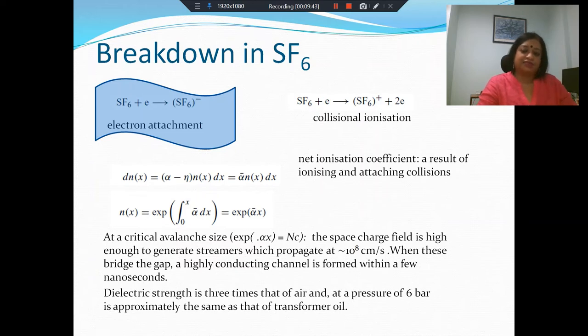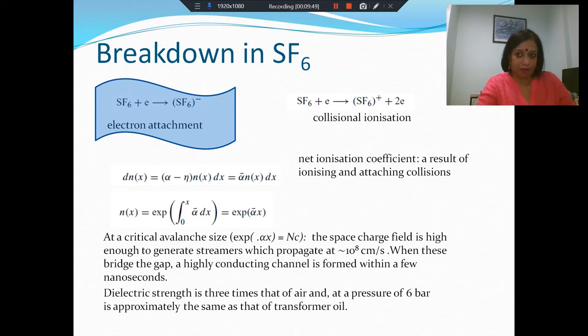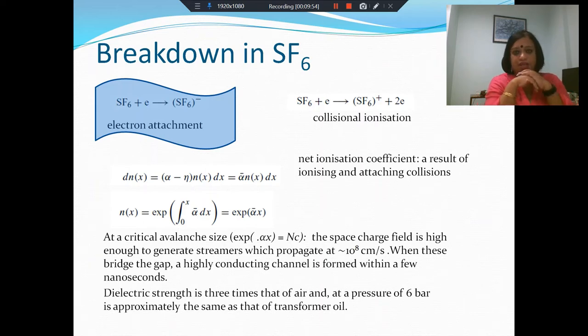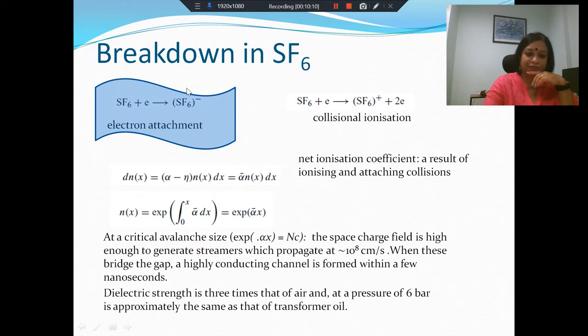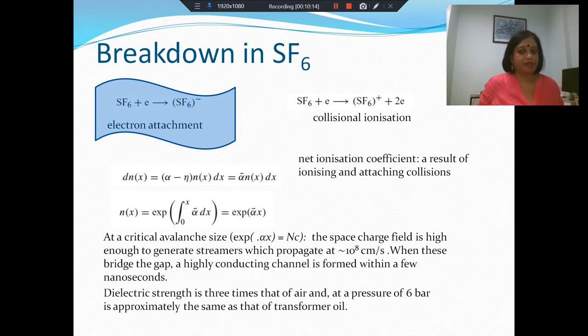The reason SF6 has very high breakdown strength is primarily because of one significant property: electron attachment. SF6 is a highly electronegative gas. If a neutral SF6 molecule collides with an electron, it will capture the electron and create an SF6 negative ion. Instead of electron multiplication driving breakdown, SF6 removes electrons from the picture.